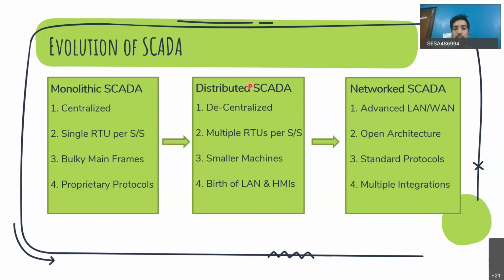Then it evolved a bit, and the second stage was called distributed SCADA. Here it started to become decentralized. Some part of the computing was done in the substation itself, and some part was done in the control center. That is decentralized computing. And then with the birth of local area networks, this is part of communication, with the improvement in communication there was this advancement so that you could connect multiple RTUs per substation, so that you could have more controlling and monitoring equipment per substation. Also in the control center, the machines became smaller, so managing them became easier. And the birth of LAN also gave rise to human machine interfaces, so that operators could easily visualize things happening in the field, and more functionalities arose out of it.